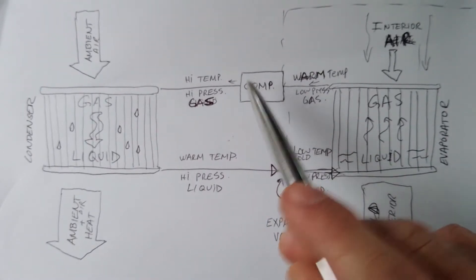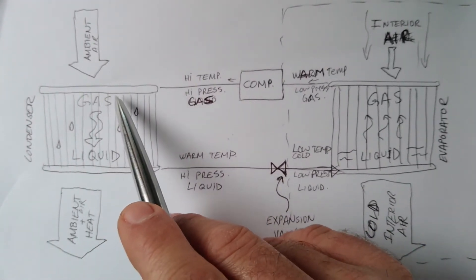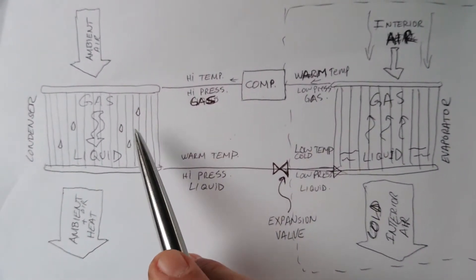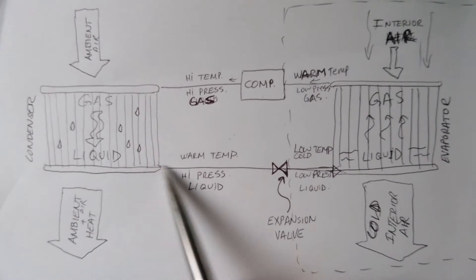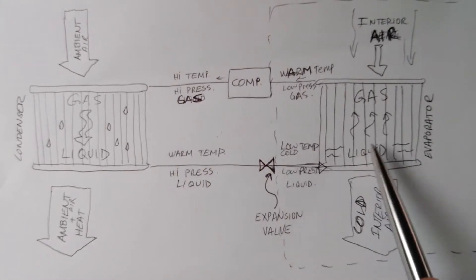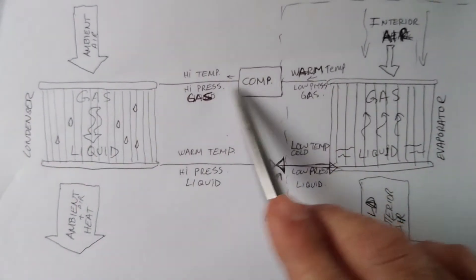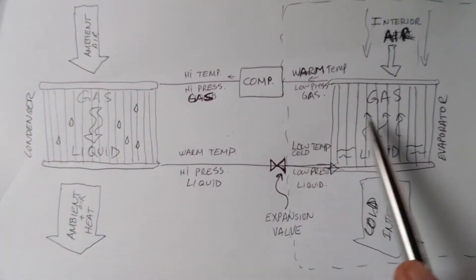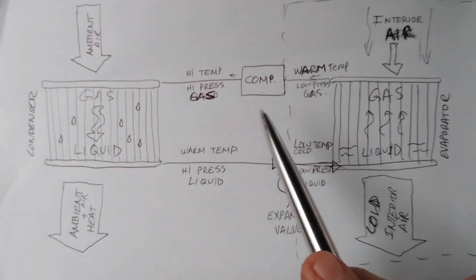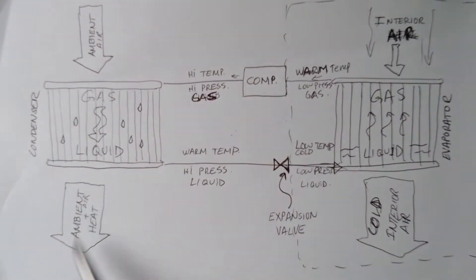Starting from the compressor: the compressor pumps the refrigerant in gaseous form, raising its temperature so it gets hot, then it goes to the condenser. Through the condenser it gets cooled — it remains at high pressure but now at a lower temperature — then through an expansion valve, then to an evaporator, and back to the compressor. The loop repeats: compressor, condenser, expansion valve, evaporator — carrying heat from inside and dumping it overboard.